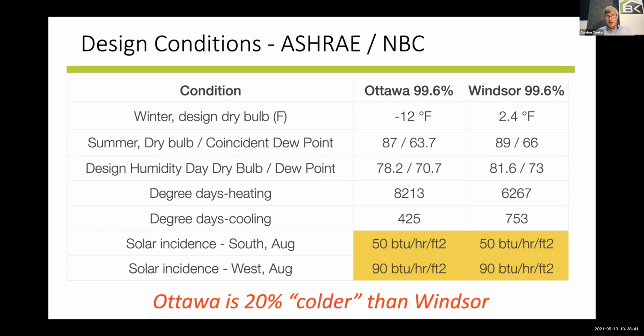Find another way to dehumidify. The next two lines down give you a sense of how cold you are for how long. That's degree days heating and degree days cooling. These are numbers that are not used in a heat loss, heat gain. That is, we don't really care how cold you are for how long. We just need to know the 99.6% day. These degree days are used in energy modeling. They're not used so much in heat loss or heat gains.